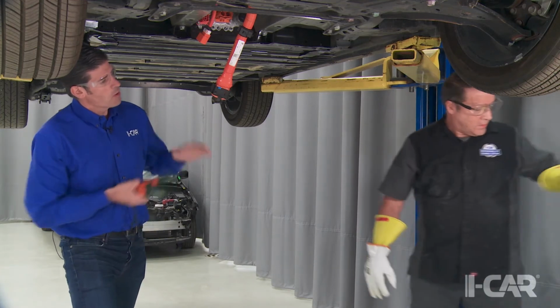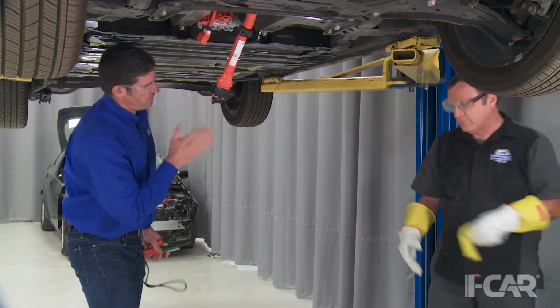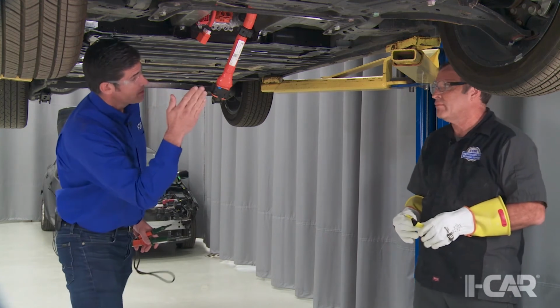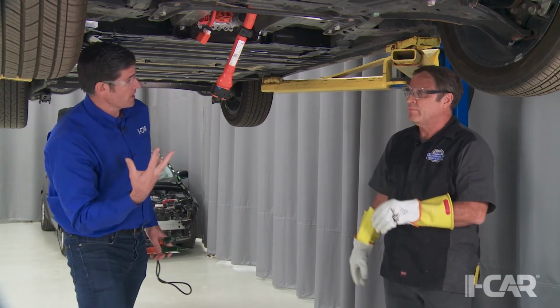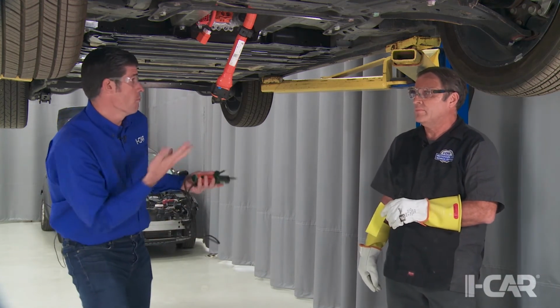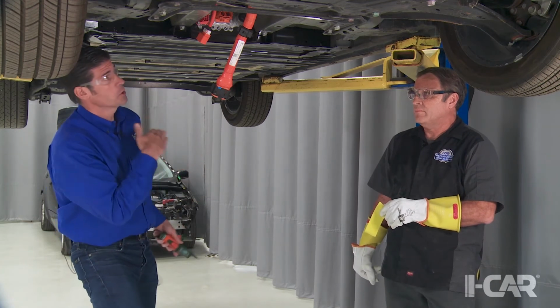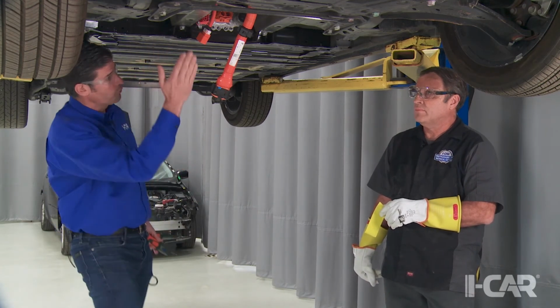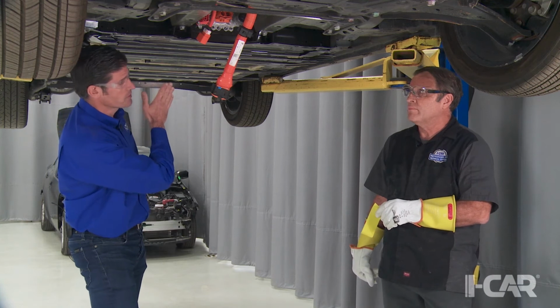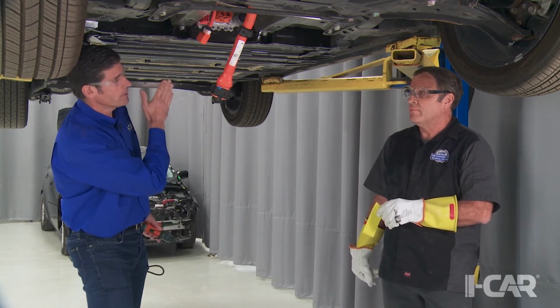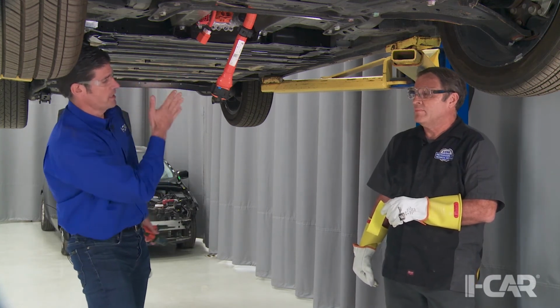I would do that every time I measure both sides. For example, for an insulation test, which we most likely will perform, you check your insulation in both directions, including toward the battery, since the potential on this side is really high.